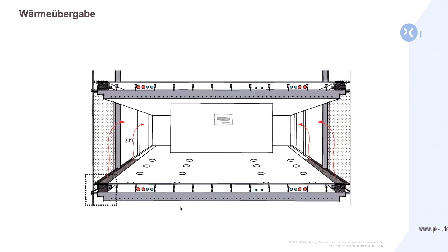The ambient air temperature requirements in this building are 22 degrees centigrade, based on the wishes of the users, and hereby underfloor convectors. If there are few persons, you can bring in heat swiftly and hand it over to the room. And the concrete core activation only amounts to a minor base load supply.